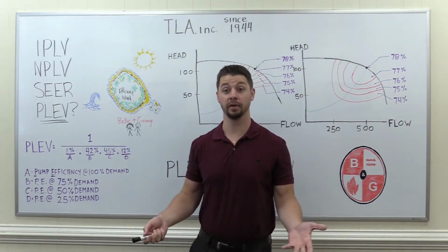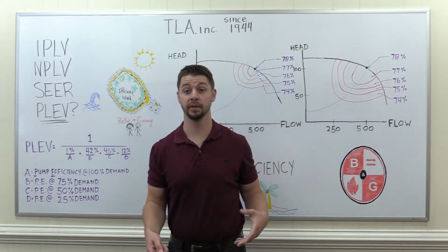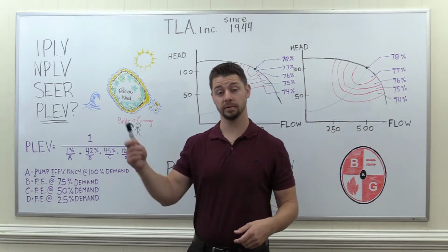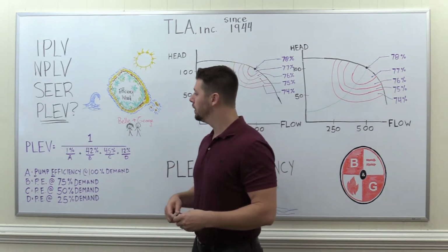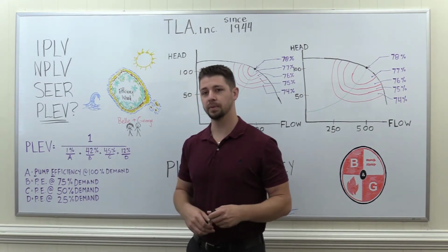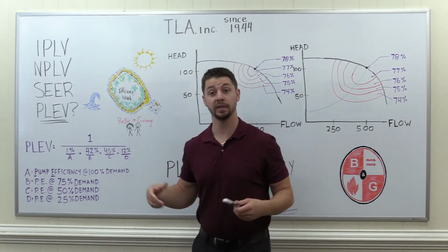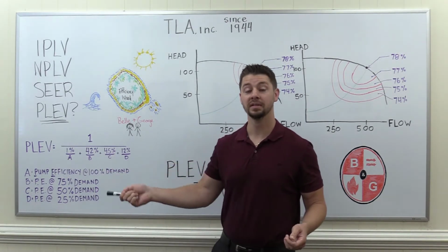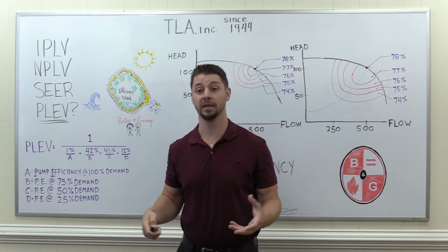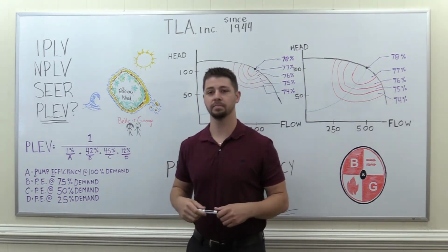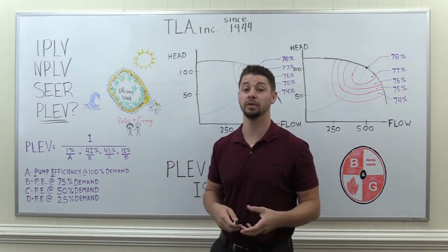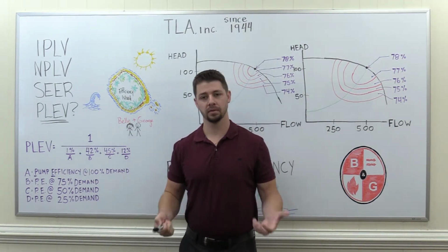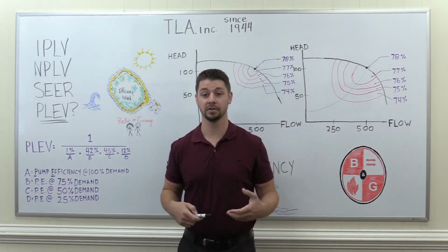And this affects variable speed pumping applications, so variable speed, variable primary chiller, primary secondary situations where the secondary pumps modulate and control flow. So the PLEV calculation is pretty simple and similar to the IPLV and NPLV, where we're actually taking the pump efficiencies at 100%, 75%, 50%, 25%, and then calculating them on this metric to come up with a part load efficiency value. We know as engineers we design for the 1%. We need to be also accounting for the 99% that our system operates.